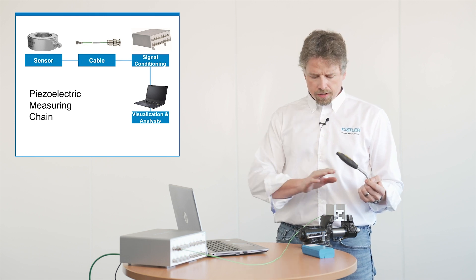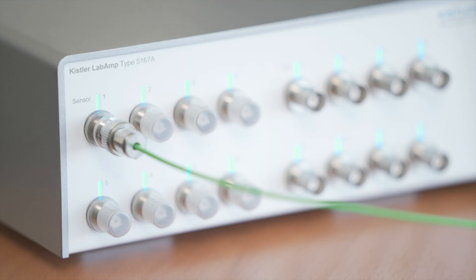As you can see now, I connected my sensor with the charge amplifier, which is the lab amp in this case, and the lab amp accordingly connected to my laptop. So I can see how much force I apply on my sensor.